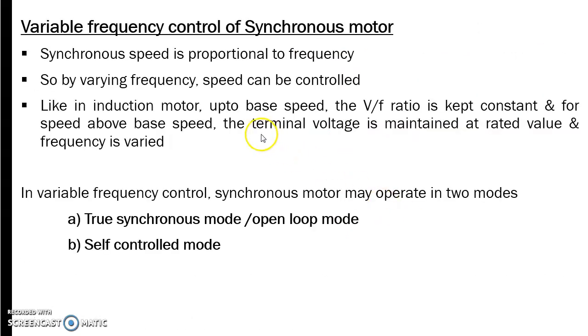And come on to the variable frequency control of synchronous motor. As we discussed in case of induction motor, variable frequency control, or V by F control, is the main method used in the drive. The same method you can implement in synchronous motor also. Synchronous speed is proportional to frequency. So by varying the frequency, speed can be controlled.